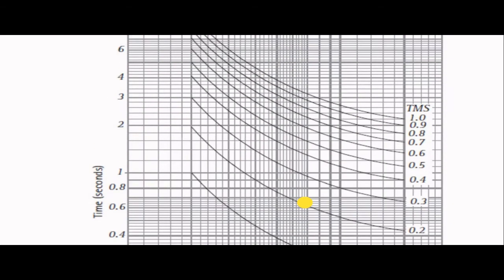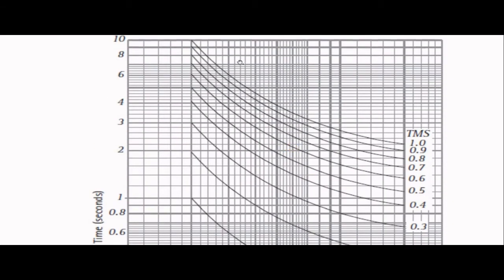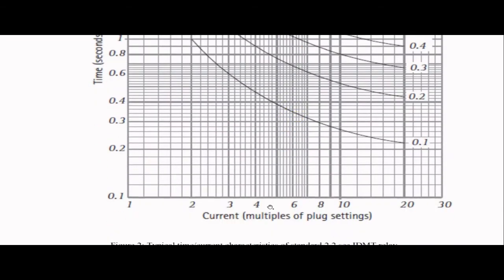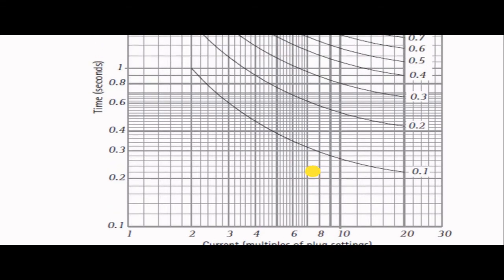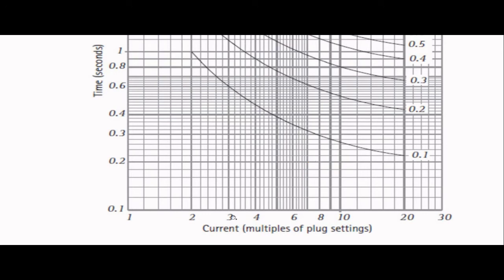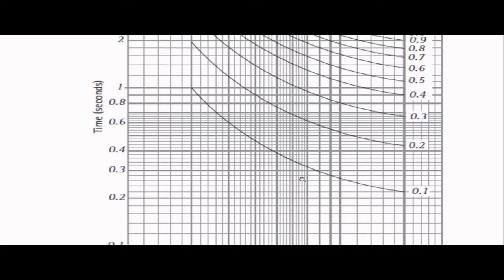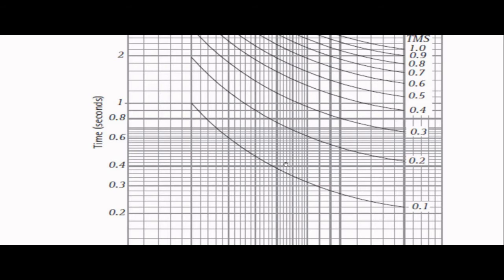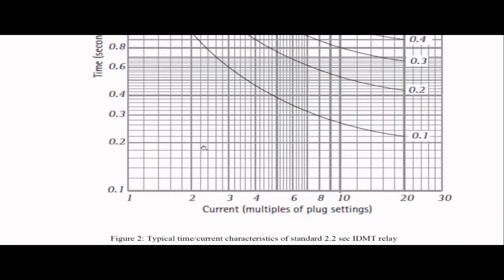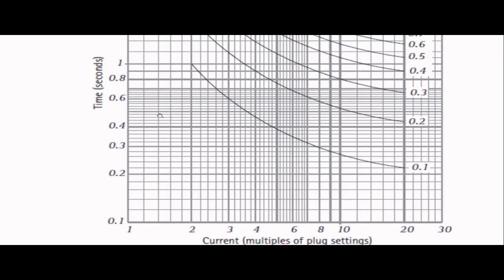IDMT means inverse definite minimum time. So why is this called inverse? Because the nature of the curve is inverse, that's why this is called an inverse characteristic. As the plug setting multiplier increases, the relay needs a smaller amount of time to generate the trip signal, because as it increases, the fault level also increases. Fault level means more fault current will flow through the fault, so this is more dangerous. So for this higher fault level, the relay should generate the trip signal quickly. That's why the nature of the curve is inverse. If the plug setting multiplier increases, the time of operation of the relay should decrease.